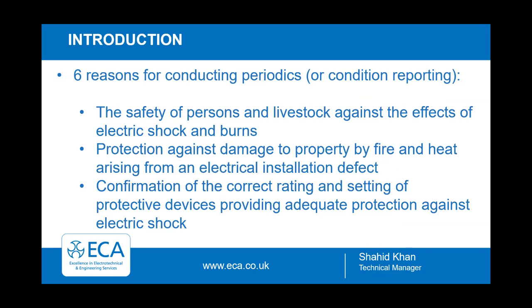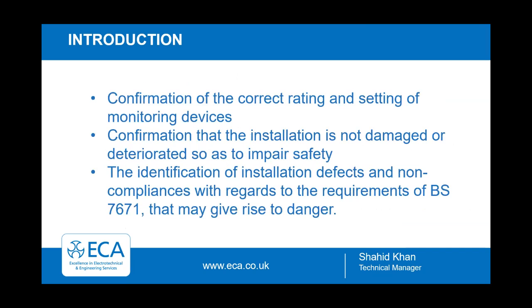These are for the safety of persons and livestock against the effects of electric shock and burns, protection against damage to property by fire and heat arising from an electrical installation defect, confirmation of the correct rating and setting of protective devices, providing adequate protection against electric shock, confirmation of the correct rating and setting of monitoring devices, confirmation that the installation is not damaged or deteriorated so as to impair safety, and finally the identification of installation defects and non-compliances with regards to the requirements of 7671 that may give rise to danger.